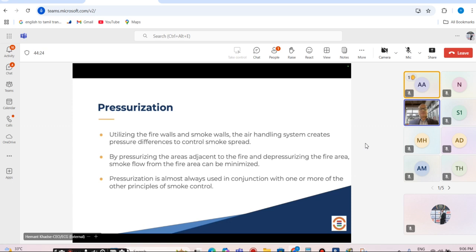The example of over-designing is that when you implement by looking at the codes and standards, pressurization is required on a specific floor, and that too, just to give an example, for a high-rise hotel building, the lobby is pressurized, the staircase is pressurized, the lift is pressurized. Now, when you have that scenario that all floors have been designed with pressurization as an option, it's the best strategy.